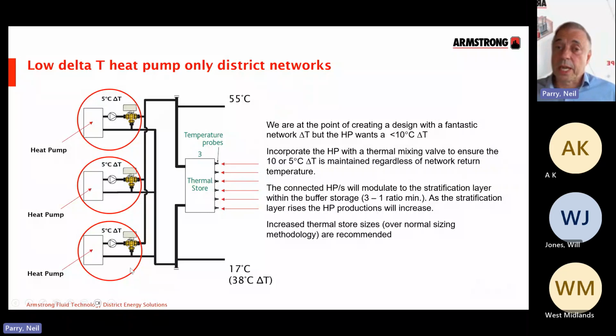Of course, the other thing this allows you to do is maybe have a peaking plant that can accept a higher delta T, and then this 3-port arrangement here can be set on that individual leg just for that one particular heat source, which could be CHP or whatever you want it to be, an electric boiler, where you maybe can accept, say, a 30-degree delta T. So you've got a nice 30-degree delta T around that energy source, but 5 around the heat pumps.